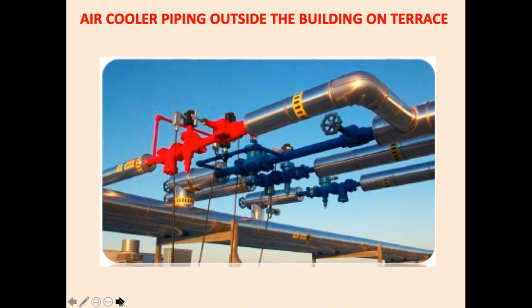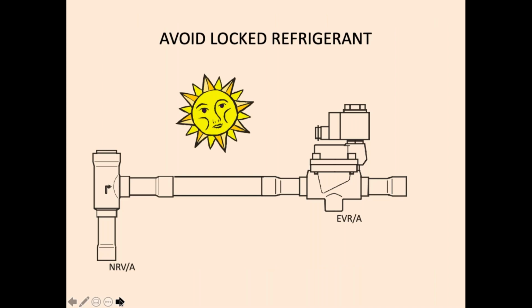I have shown you this photograph, how to do the piping. There is a walkway on which you can walk and adjust your piping. This is a very important suggestion. Avoid locked up liquid refrigerant. Liquid refrigerant is not compressible or expandable. And what happens? You have a non-return valve. Here there is a solenoid valve.